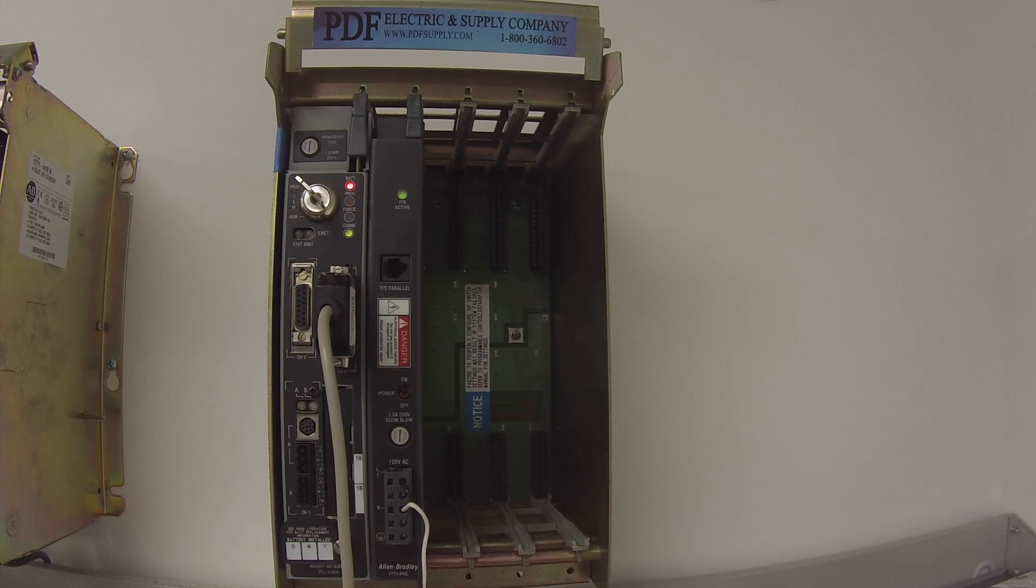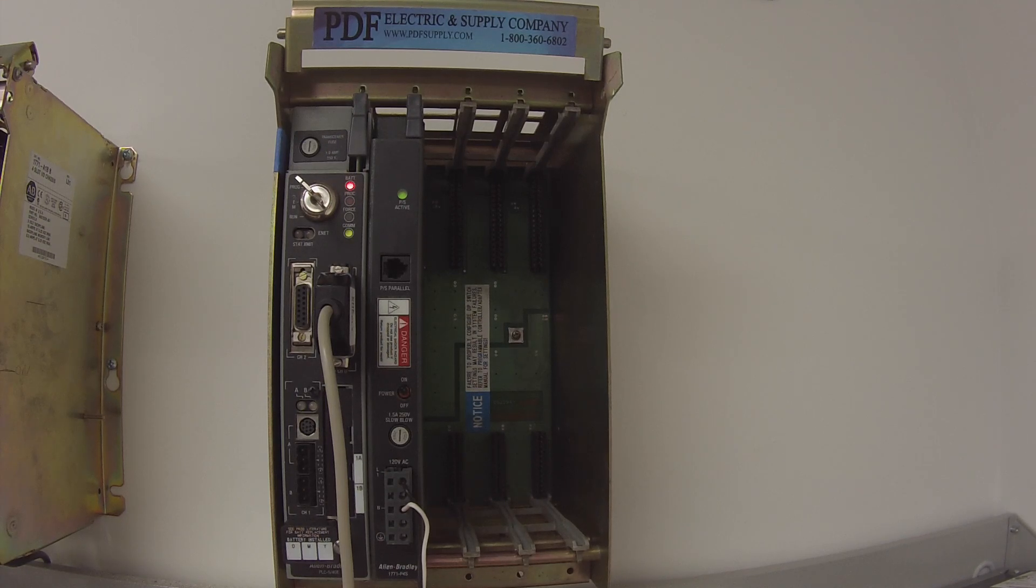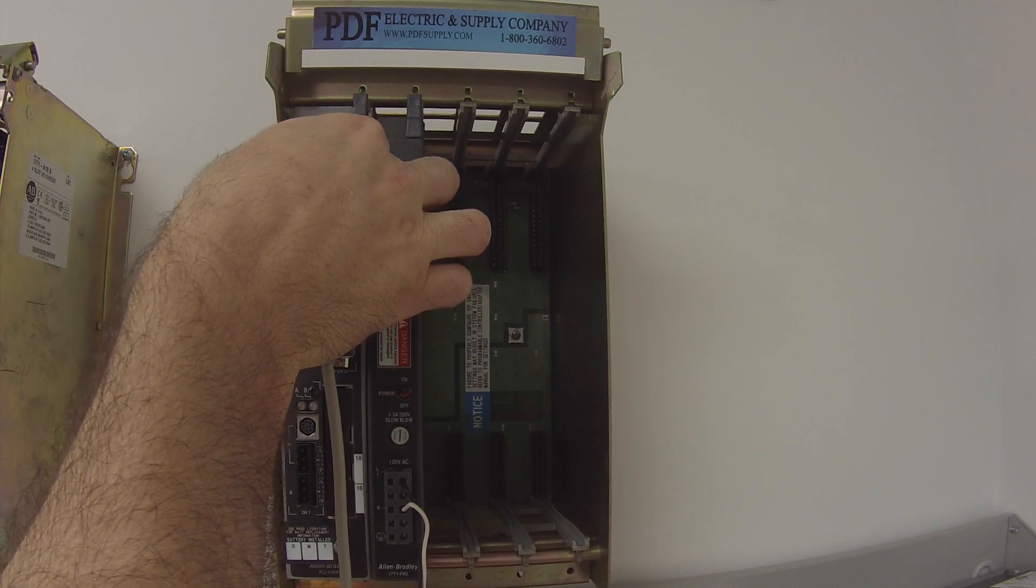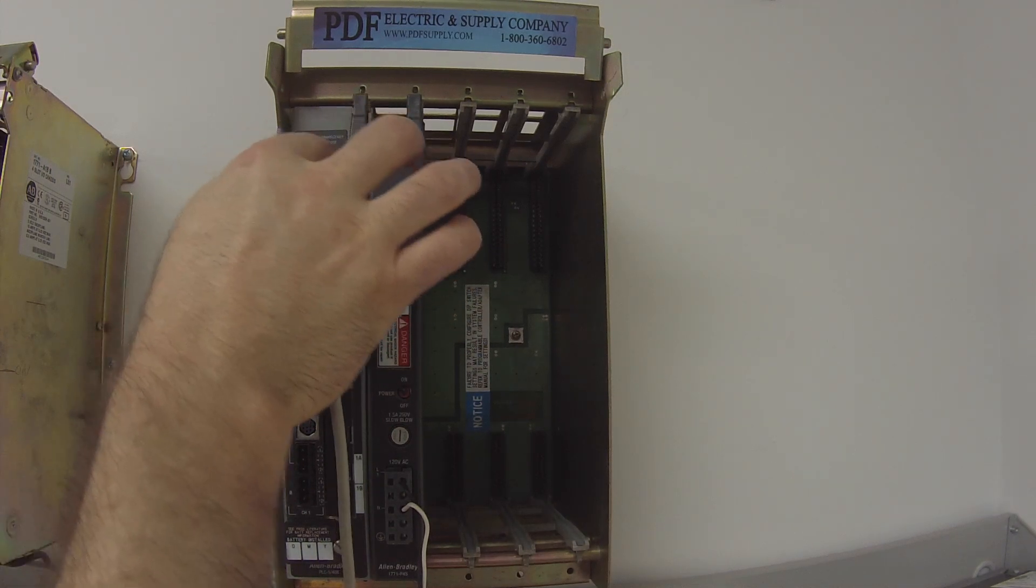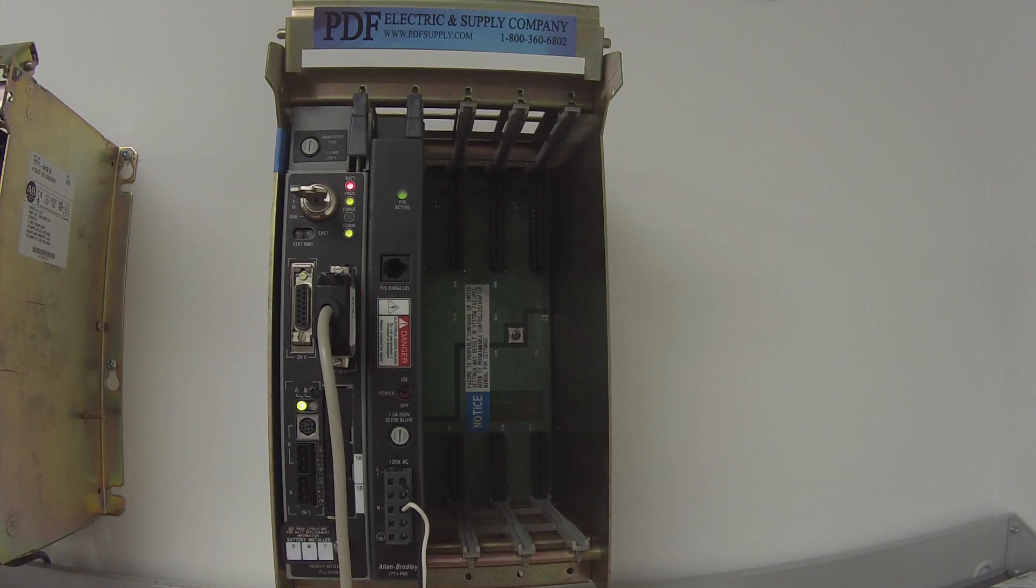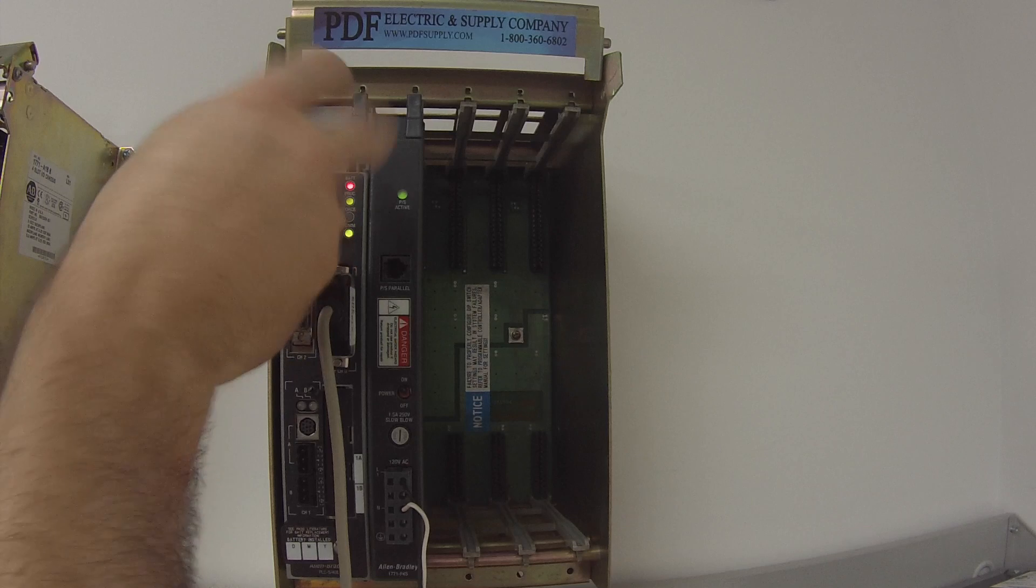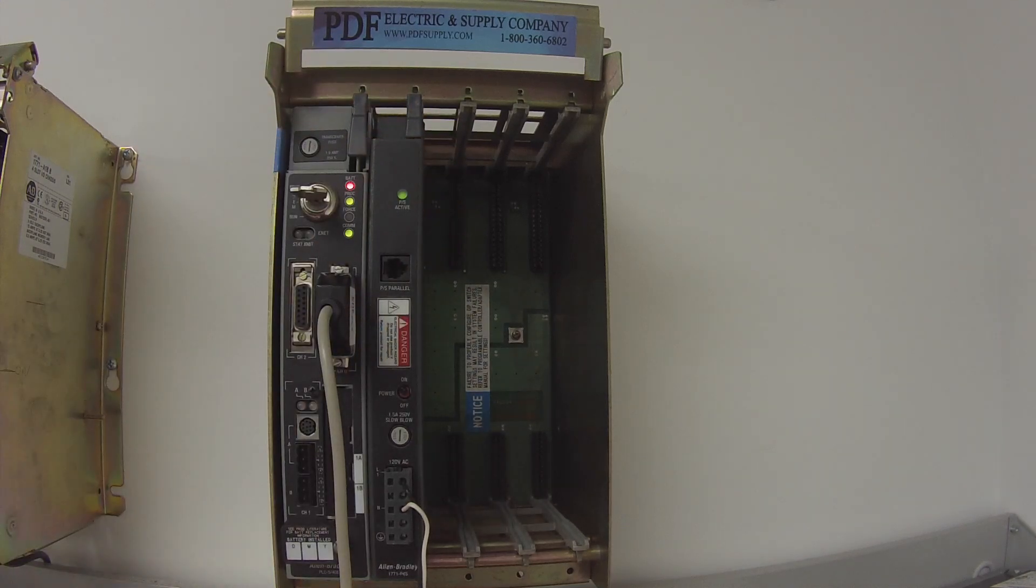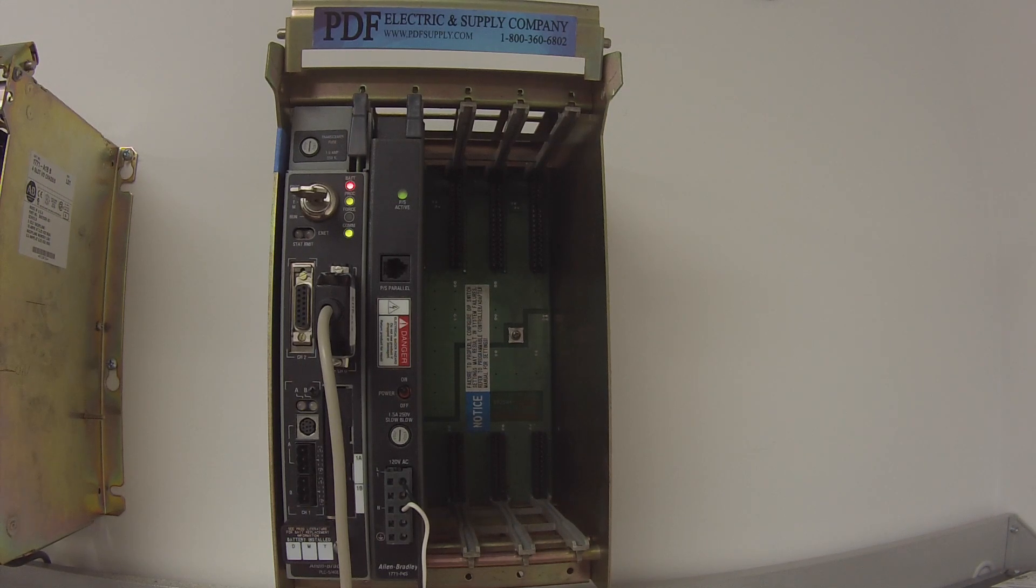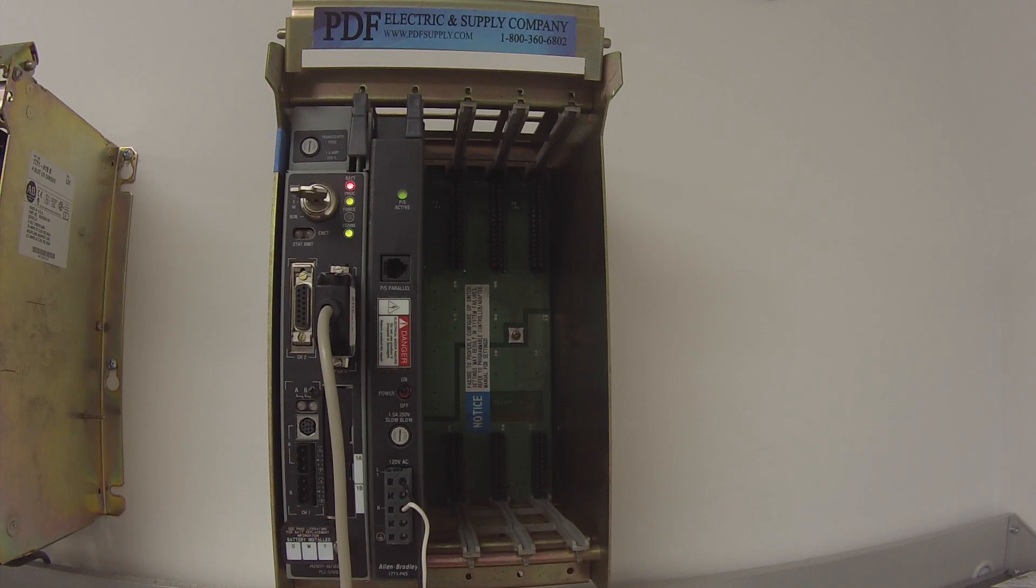All right, so now that I'm online, where it used to say offline on the top left-hand side of my screen, it now says program, so naturally what I'm going to do is turn this to remote program, hard run, back to remote run. For a test, you don't necessarily need the hard run, but you want to go all the way through and back to make sure that on your computer screen, on your software, it shows that you're green and in run mode and not faulted. So remote run is what I normally use to test this processor.